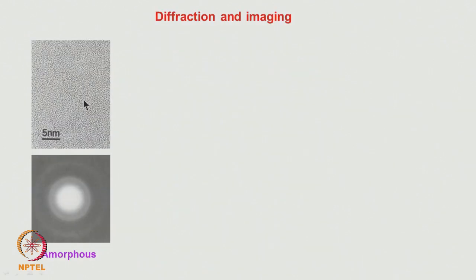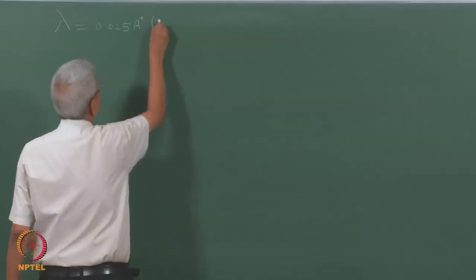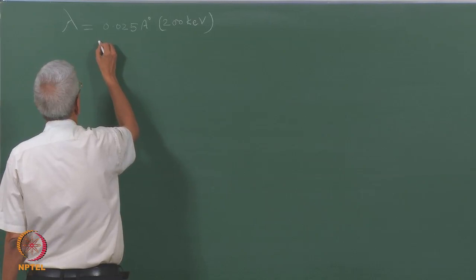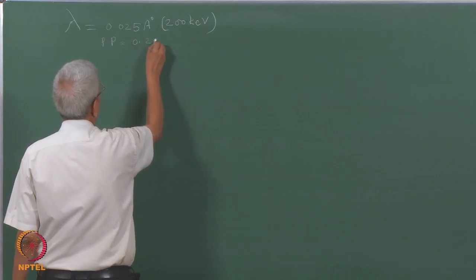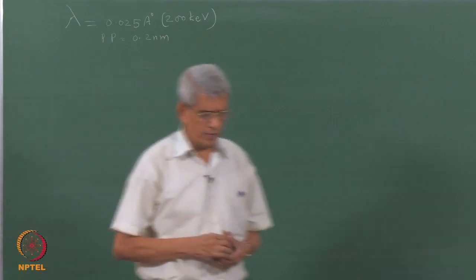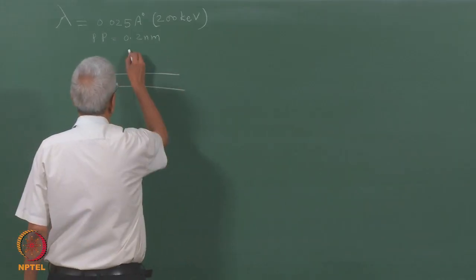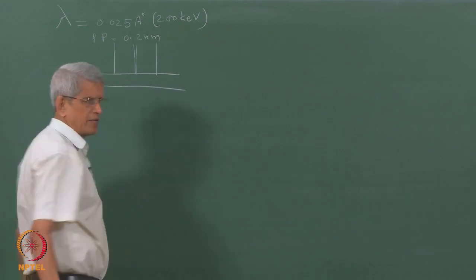The microscope can be operated at different length scales. The wavelength of the electron beam is of the order of 0.025 Ångströms for 200 kV radiation. Due to various lens aberrations, the point-to-point resolution in a conventional microscope is of the order of 0.2 nanometers. Since it is an electron beam, we can focus it to a very small area or spread it over a very large area — these are all advantages of working with a lens.